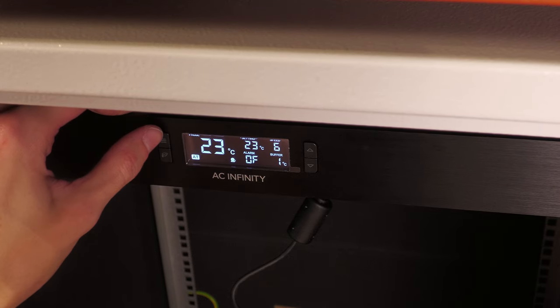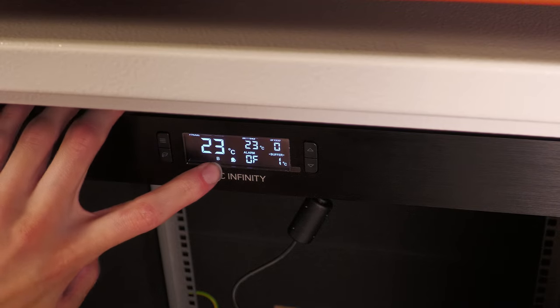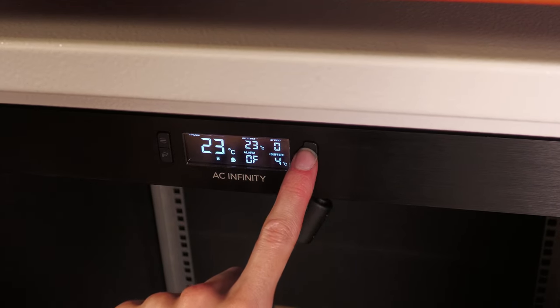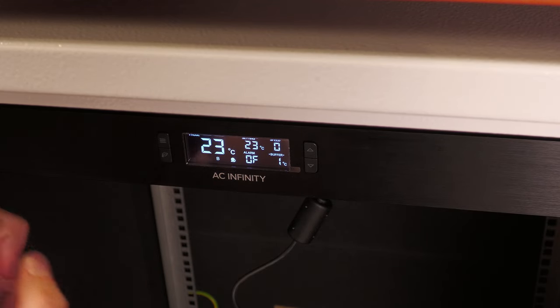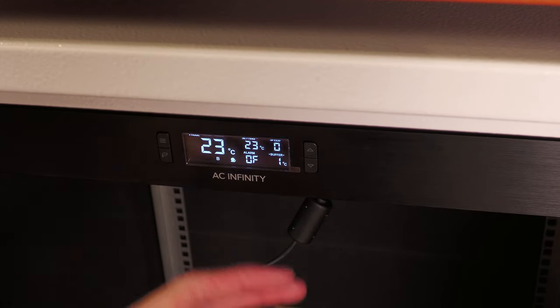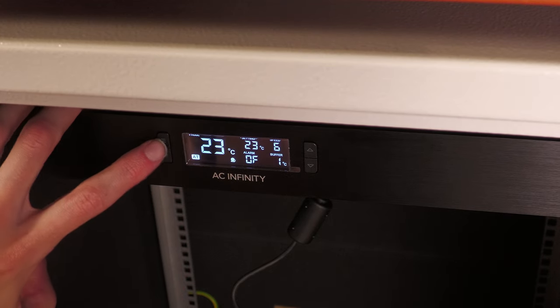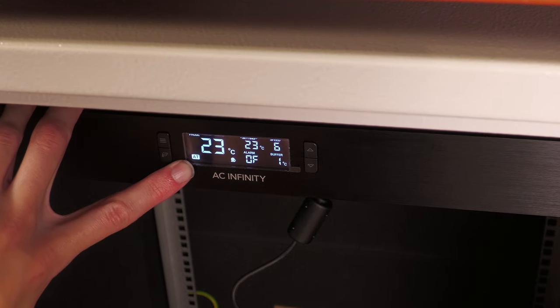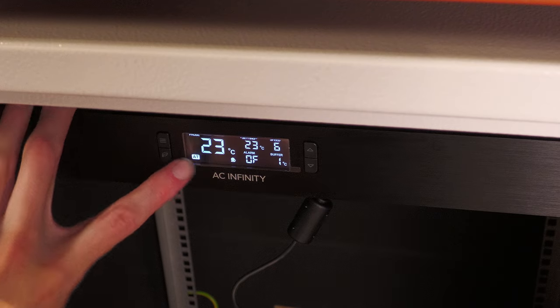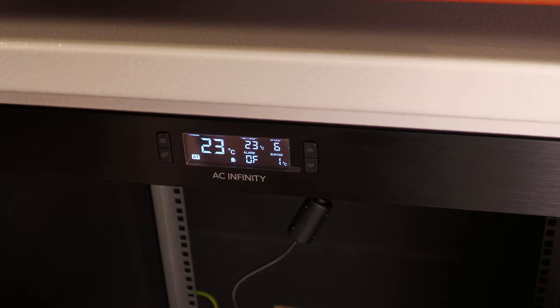The final mode you'll see here is buffer. So if you go along to buffer, which is B, that's this temperature here. And you can set this between 1 and 4 degrees. It's a buffer around how quickly the fan speeds will change. So when you're using it on auto thermostat mode, this is how much the temperature needs to change for the fans to turn on or off.